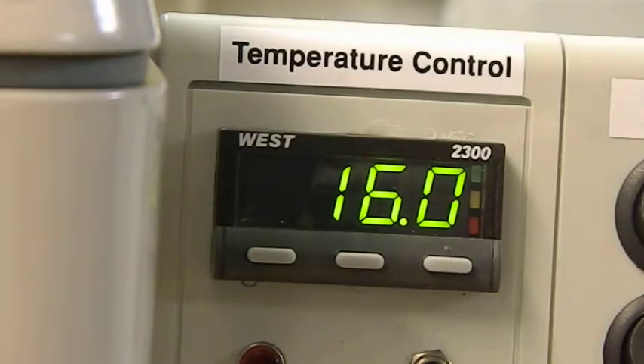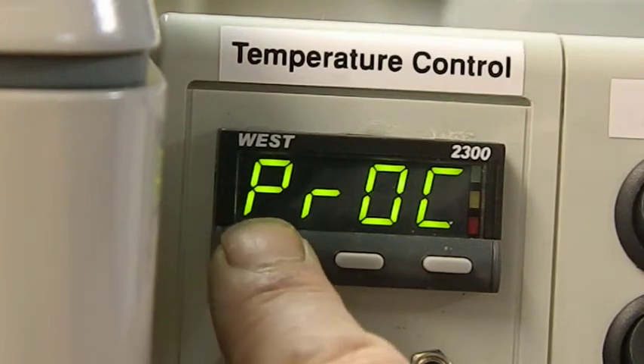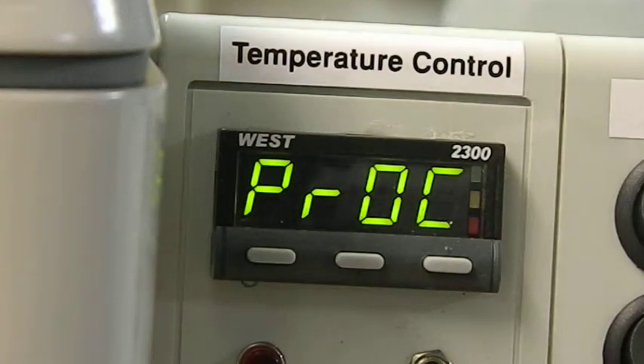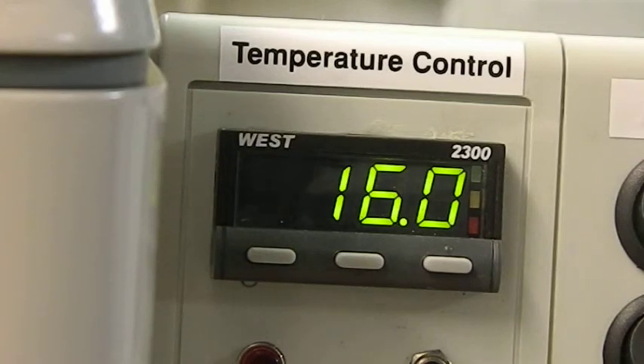At this point we would then take the set point up to whatever incubation temperature you're looking for. So you go flick through the parameters again until you get to SP, and you change that up to whatever figure you want to run at. This one's flicking 16.0 to 16.1, so it's very close. So what I would suggest you do with this particular machine, and what we would do with it here on test, is we would run it up to incubation temperature of 37.5, and we would go through that again just to check that it was within 0.1 of a degree. 9 times out of 10 they are.